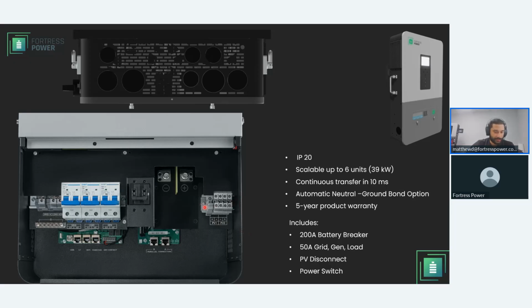And then the reason why I say that is because I know they're inverted on MPPT2, so just keep in mind when you're installing MPPT2 or PV1 that you don't get a positive, negative, positive, negative. It should be positive, negative, negative, positive. Okay, you have your communication port on the bottom, parallel B and parallel A. So when you go from inverter to inverter, you're going to start from parallel A with an RJ45 cable that's included within the inverter, and then connect to the other inverter landing on parallel B.